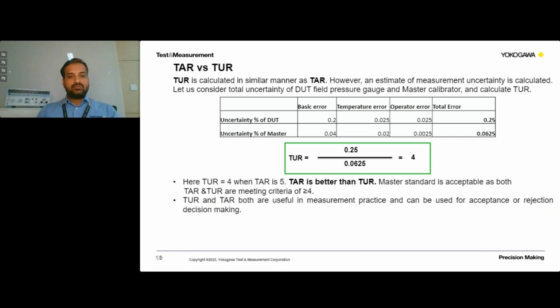And when it comes to decision making, TUR and TAR both are useful in measurement practice and can be used for acceptance and rejection decision making. So when it comes to a calibration lab or any of the process industry, to make a decision whether the DUT is fit for installation in the field, or whether the DUT is fit to be used for any of the application, that decision can be made by checking test uncertainty ratio as well as test accuracy ratio. Both are considered.